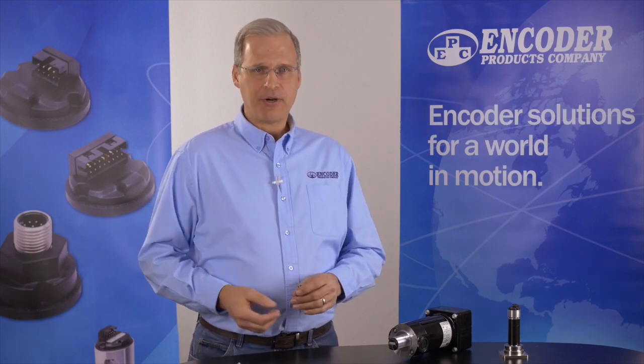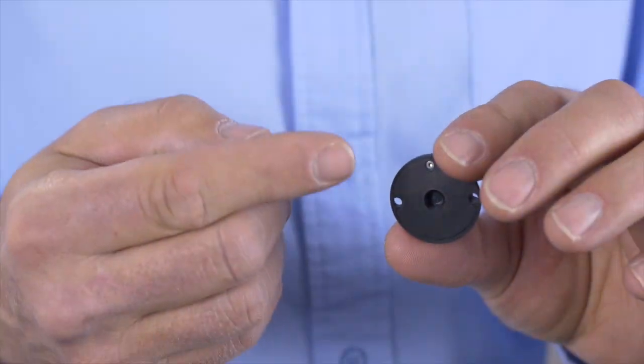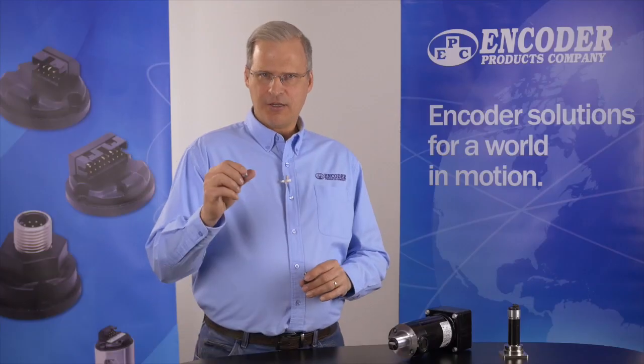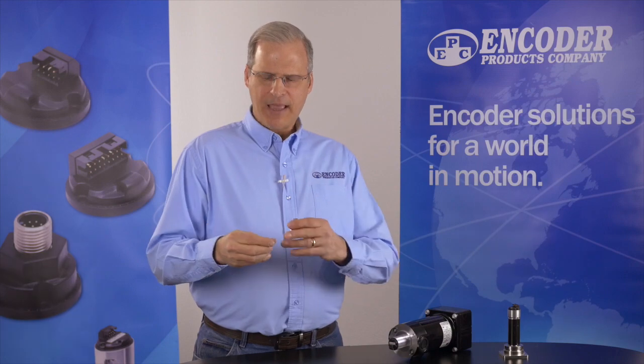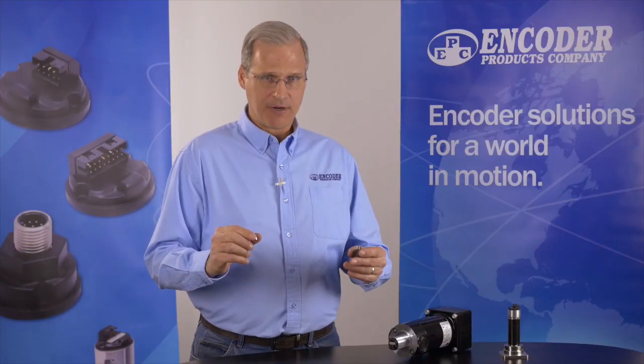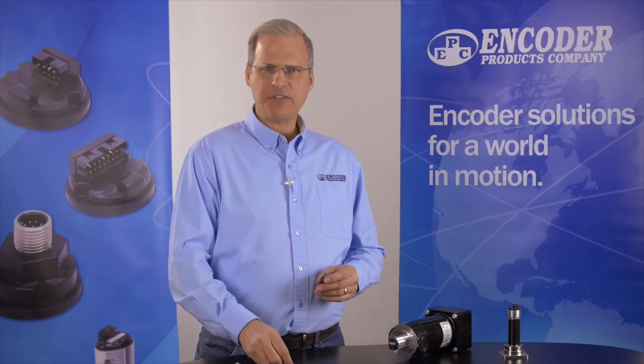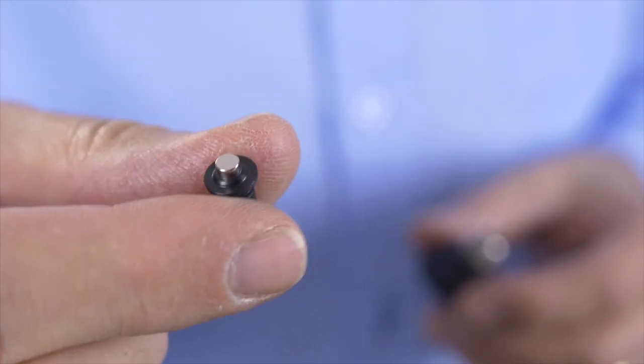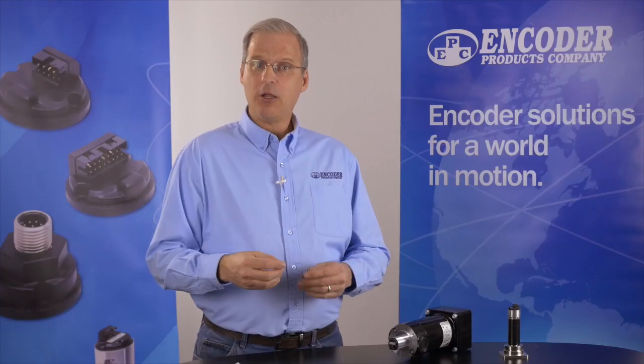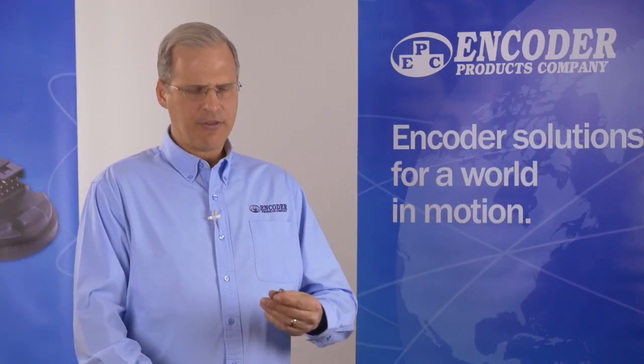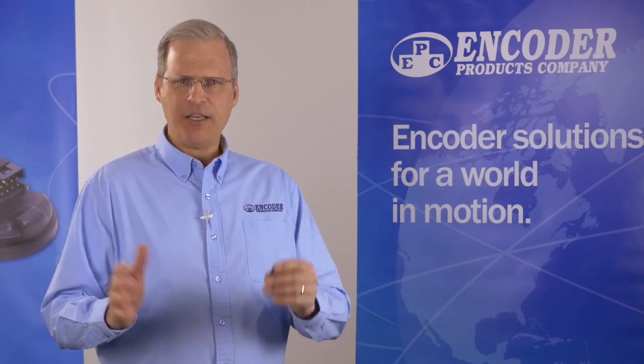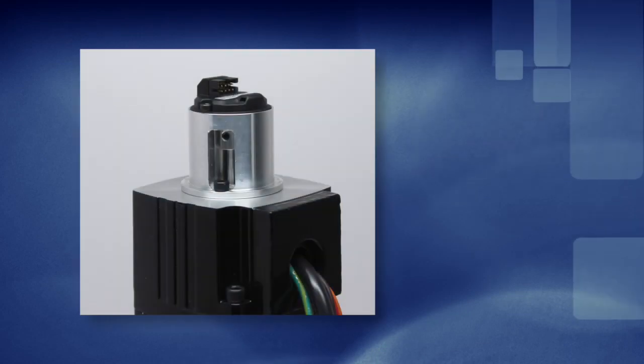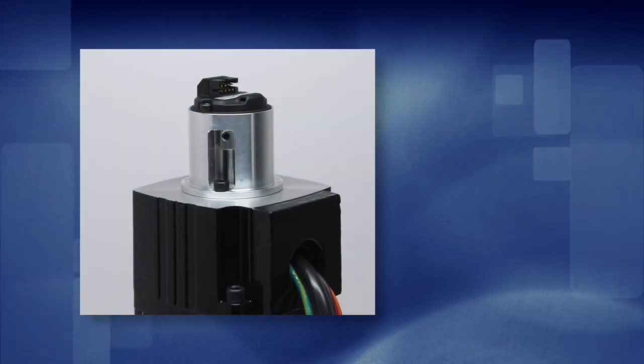The Model 30M consists of the housing module containing the Hall-Effects sensor and related circuitry and a separate end-of-shaft magnetic target. The magnet is typically applied via an over-shaft magnet holder available in several sizes or an insert that is designed to press fit into a quarter-inch diameter bore. The insert can also serve as an over-shaft holder when applied to a one-eighth inch diameter shaft. The 30M module can be quickly and easily mounted to a motor housing adapter or any fixed surface that maintains the required sensor-to-magnet air gap and alignment.